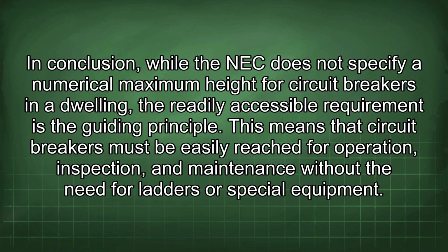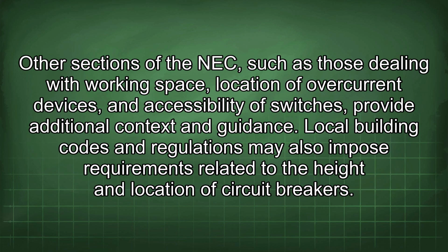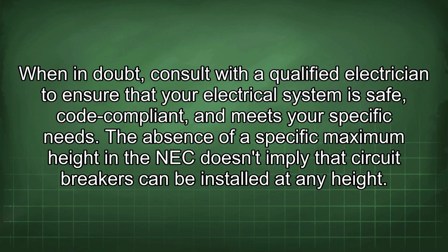In conclusion, while the NEC does not specify a numerical maximum height for circuit breakers in a dwelling, the readily accessible requirement is the guiding principle. This means that circuit breakers must be easily reached for operation, inspection, and maintenance without the need for ladders or special equipment. Other sections of the NEC, such as those dealing with working space, location of overcurrent devices, and accessibility of switches, provide additional context and guidance. Local building codes and regulations may also impose requirements related to the height and location of circuit breakers. When in doubt, consult with a qualified electrician to ensure that your electrical system is safe, code compliant, and meets your specific needs.